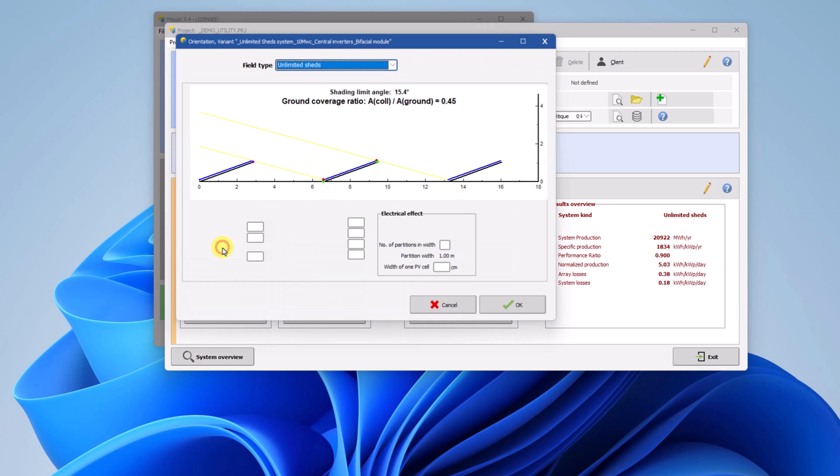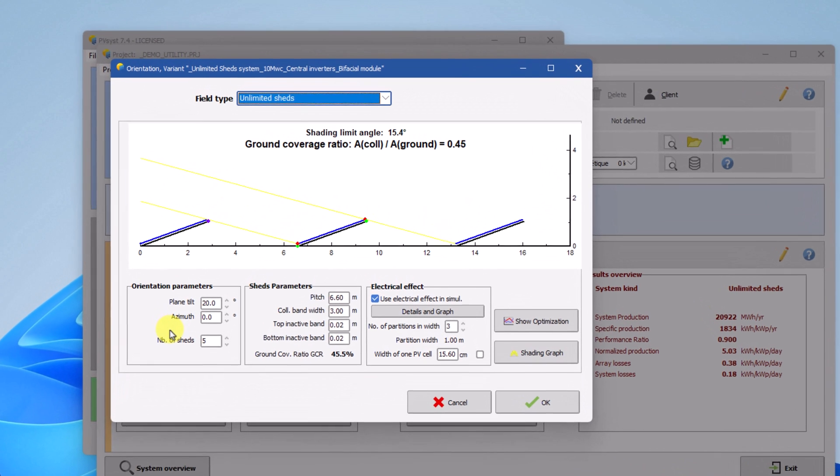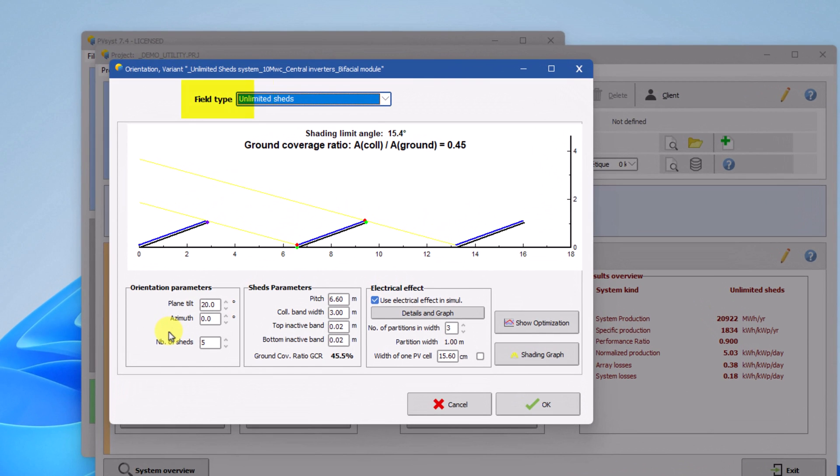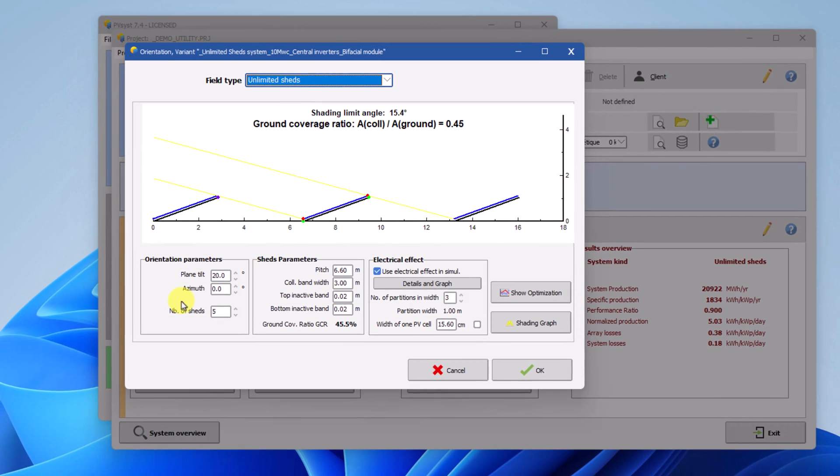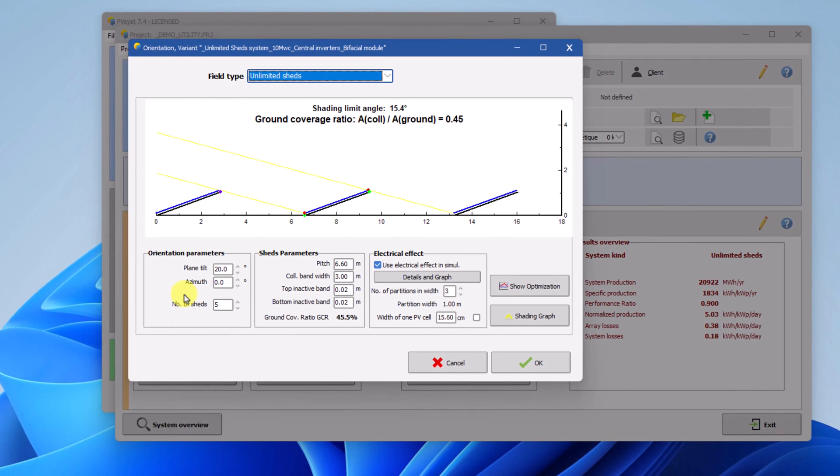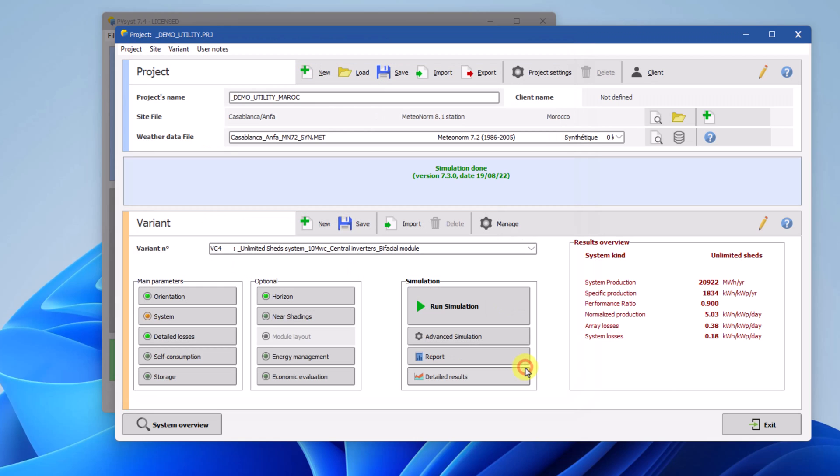The variant VC4 uses the unlimited sheds orientation. This is a simplified representation of fixed tilt rows which allows to calculate the mutual rows shading without the need of detailed 3D models of the PV installation. This simplified 2D model approximates well large and regular row based systems. It neglects edge effects at the side extremities of all rows and behind the last row. Click OK to come back to the project dashboard.